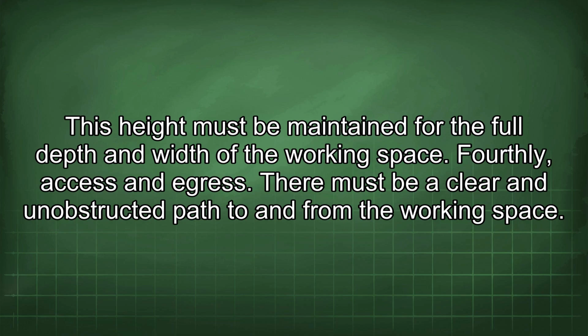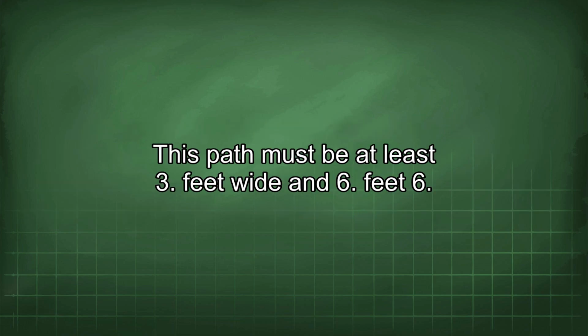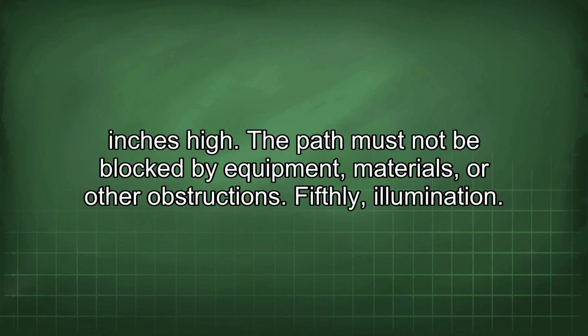Fourthly, access and egress. There must be a clear and unobstructed path to and from the working space. This path must be at least 3 feet wide and 6 feet 6 inches high. The path must not be blocked by equipment, materials, or other obstructions.